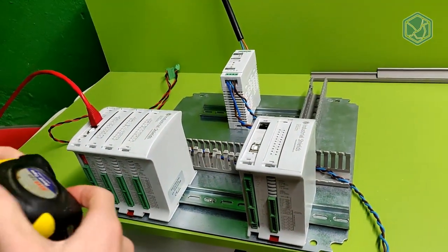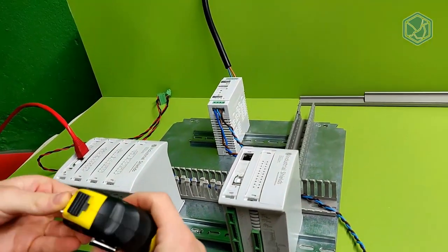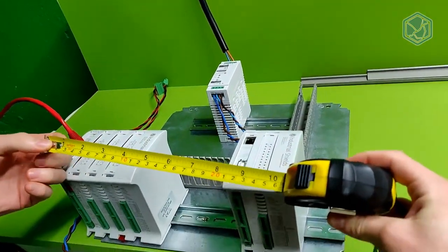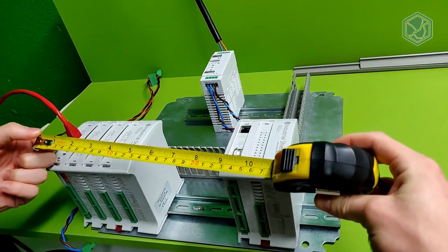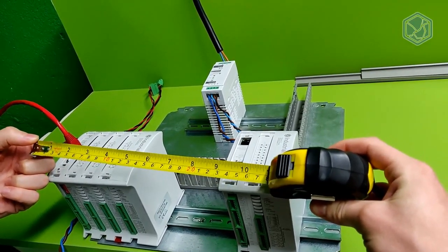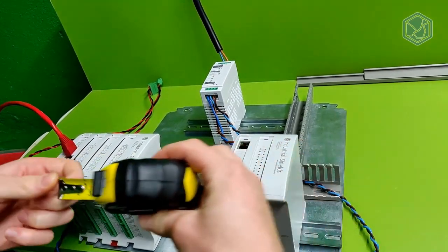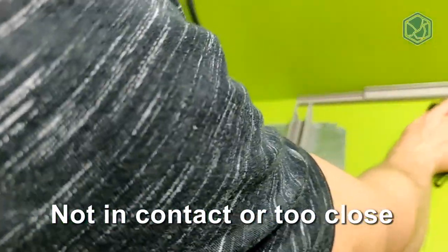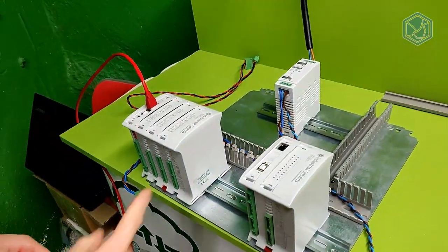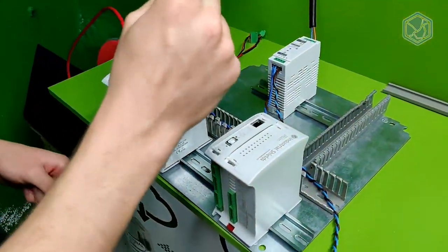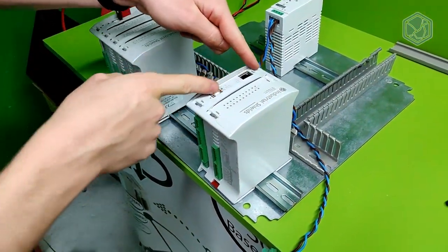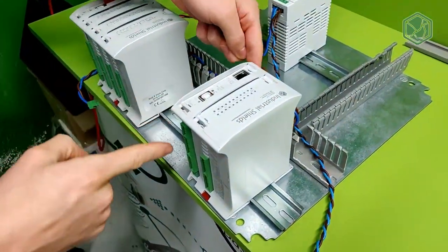In the case that the devices are closer than the safety distance, be sure that the external power source or the PLC's power source part are not in contact or too close to the PLC's board part, because the board will raise its temperature and it will turn off for safety reasons.